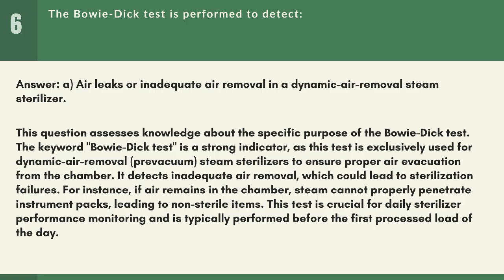It detects inadequate air removal, which could lead to sterilization failures. For instance, if air remains in the chamber, steam cannot properly penetrate instrument packs, leading to non-sterile items.